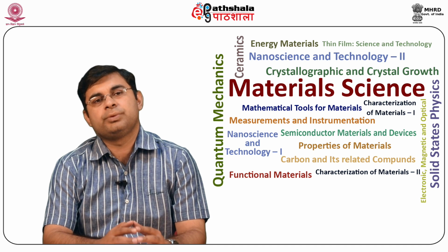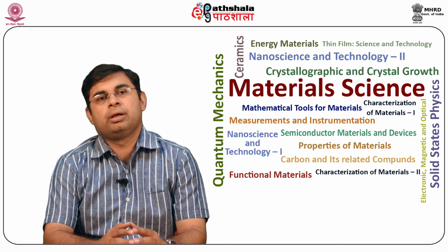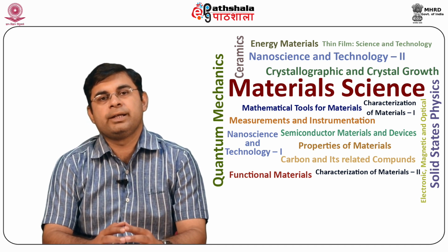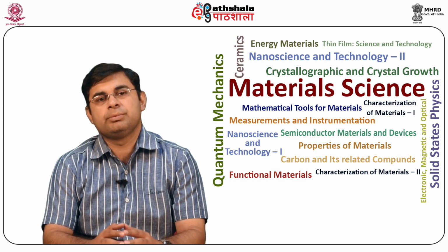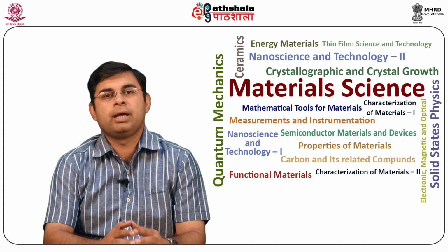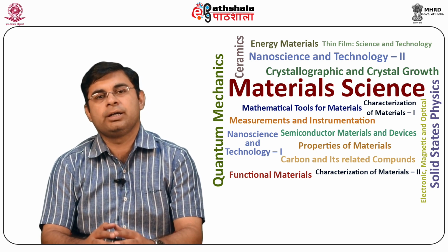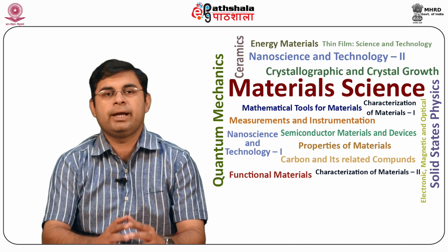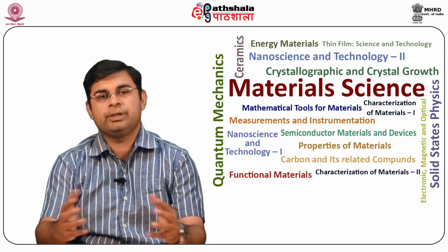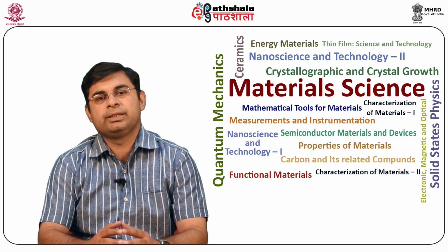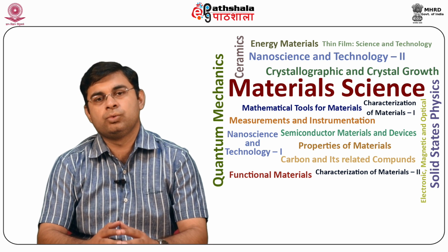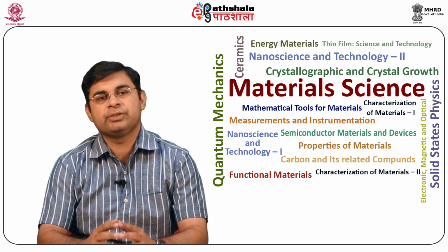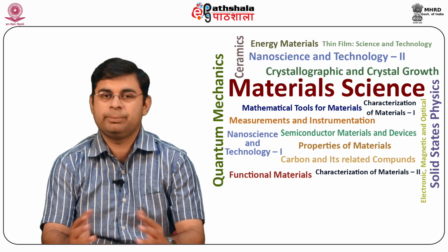Platinum is the most preferred material in laboratory work and industrial measurements of high accuracy. Platinum is commercially available in pure form and is relatively stable under different environmental conditions. Its resistance curve is simple and holds true over a wide range of temperatures, that is, minus 163 degrees centigrade to plus 545 degrees centigrade, that too with high precision.